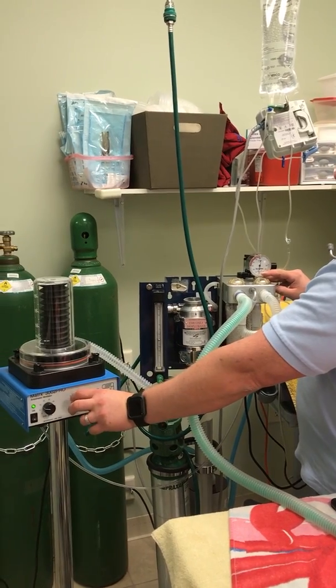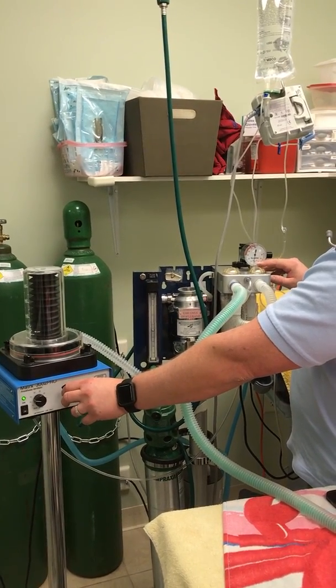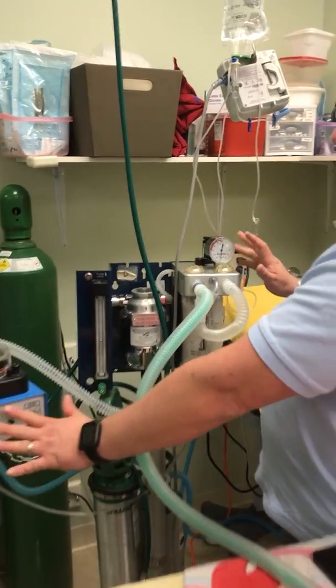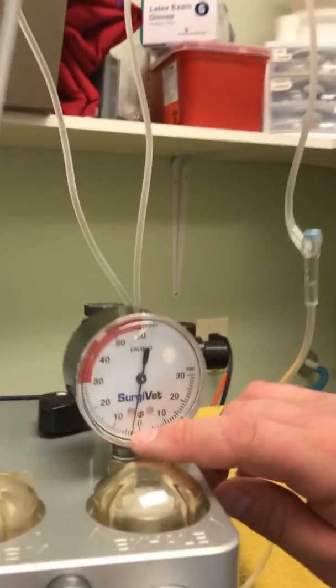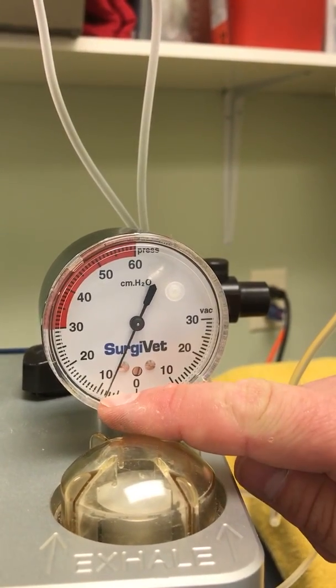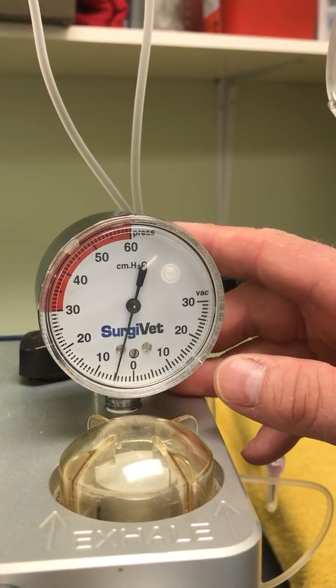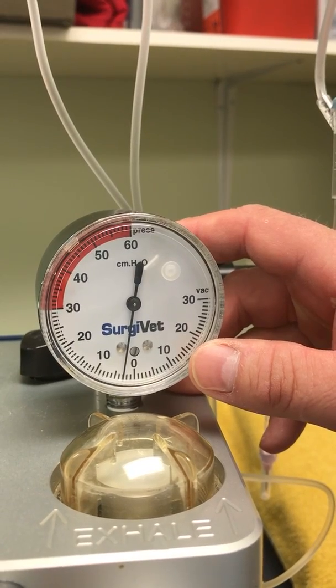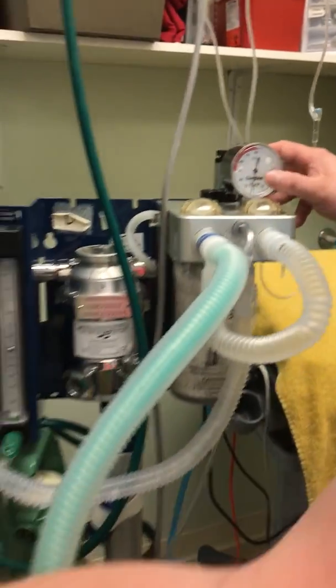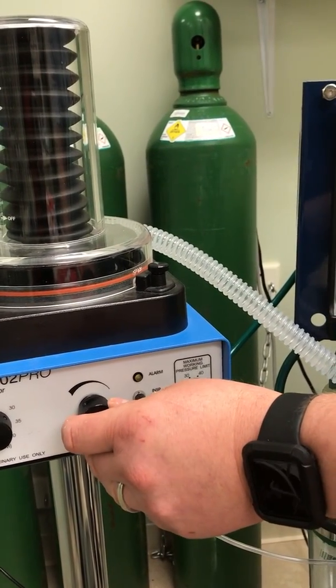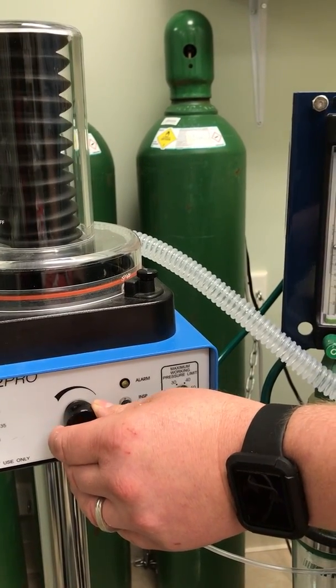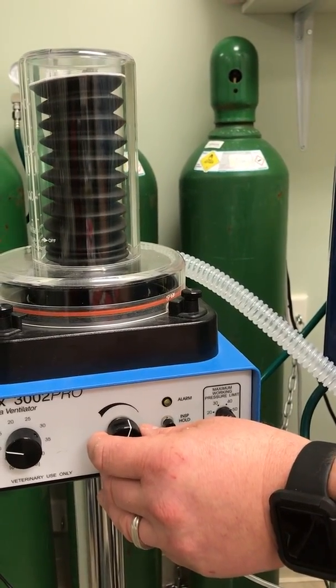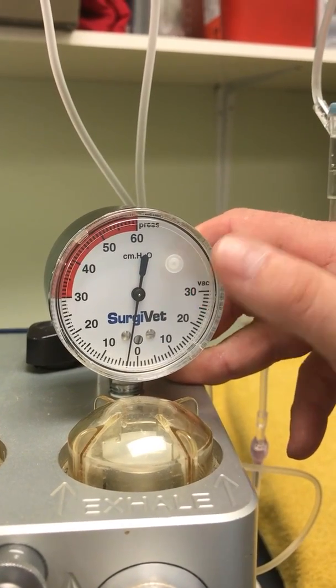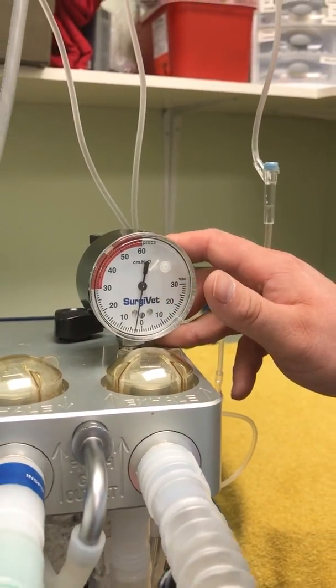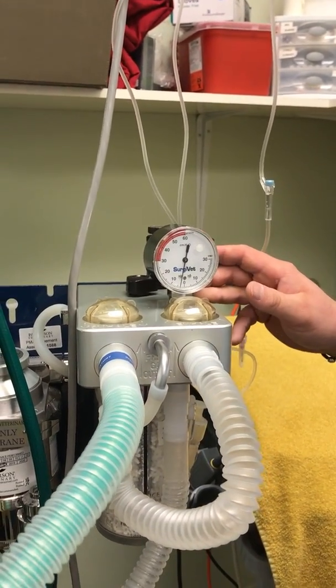And so we keep turning up the volume flow meter, and once we hit above about 5, the alarm shuts off. But we do want to make sure that we get above 10. So the alarm is off now, and we get up to about 7 or 8. So we want to go up a little higher. And we only see the maximum pressure when it's forcing an inspiration. Okay, so now we've managed to get our number here on the pressure machine up to about 12, and that will serve for our patient inspirations under pressure.